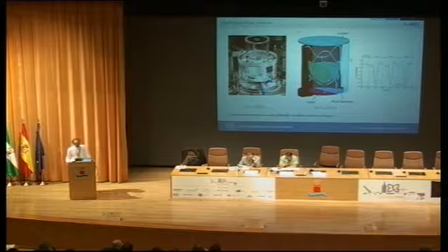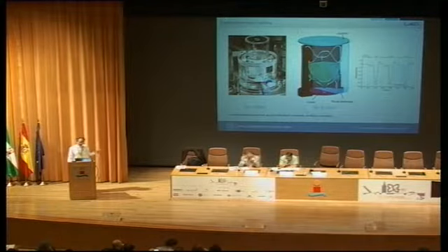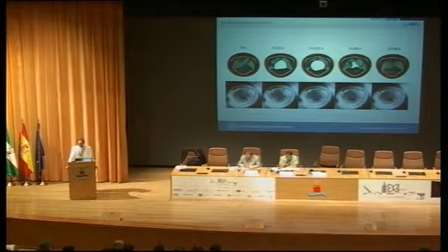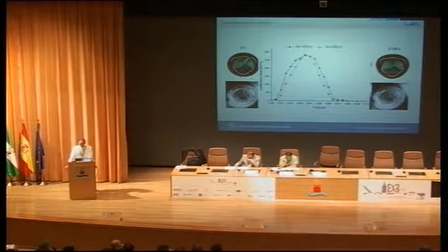The blue one represents the fluid. And the boundary condition in this case is the pressure gradient that has been measured during the in vitro test. We want to make a replica from a computational point of view of the experimental test. And we did this comparison in terms of opening area of the leaflet. Here you can see the in silico on the top and the in vitro on the bottom. And we measured the area at the maximum opening. We have a really good agreement, while during the cycle there was some discrepancy.